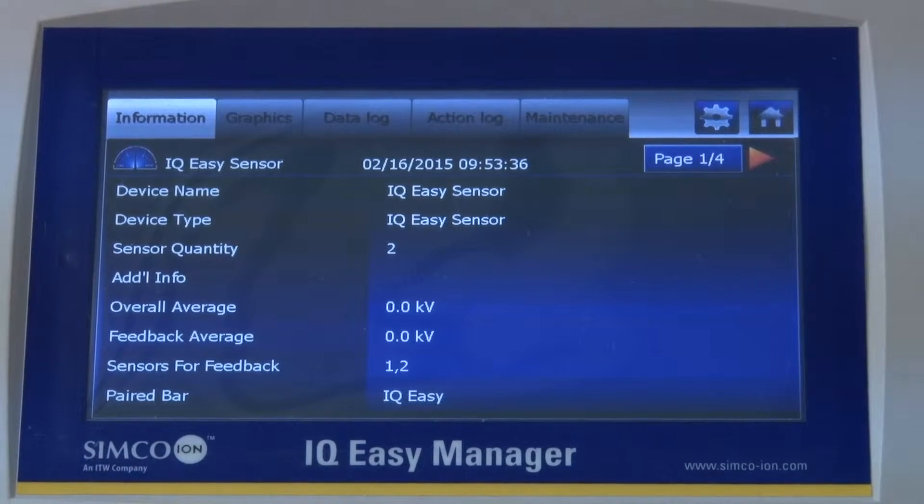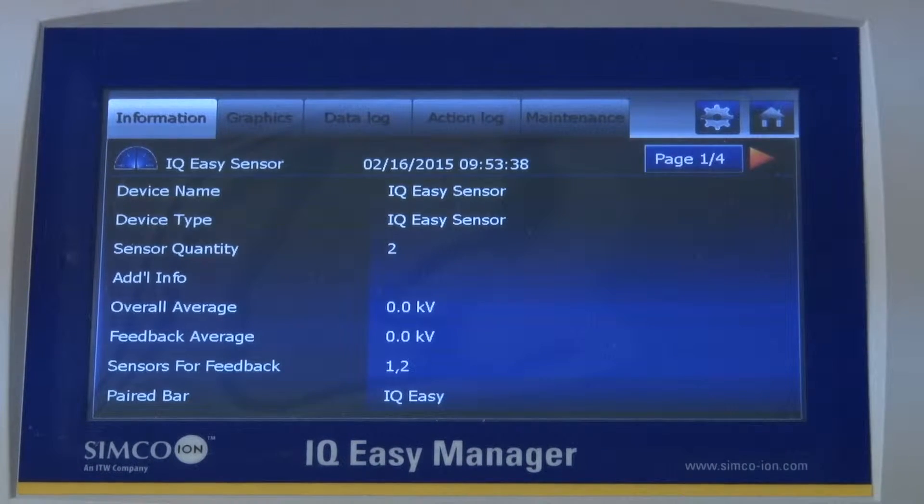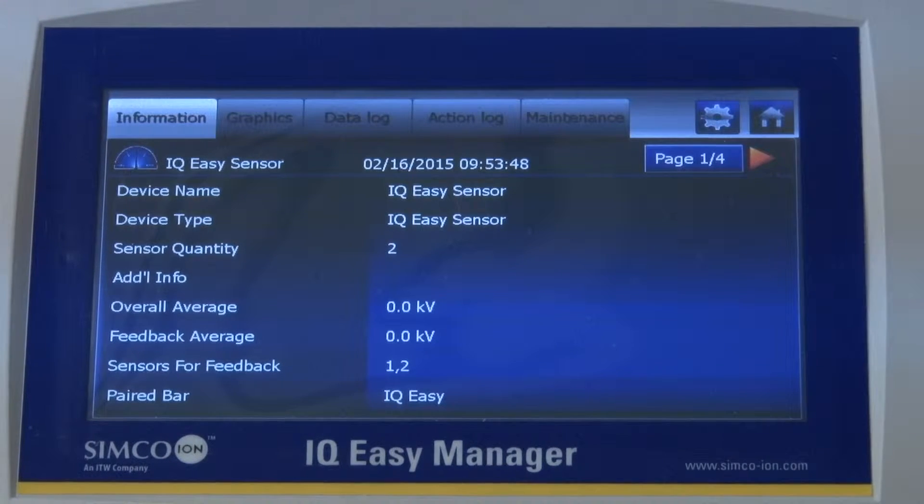Okay, we can see now that as we run, the closed-loop feedback system responds. And now this metric here, which is our closed-loop feedback average, these numbers are zero now. So that shows that the web has been completely neutralized to the best of the ability of the sensor bar in closed-loop feedback with the neutralizing bar.